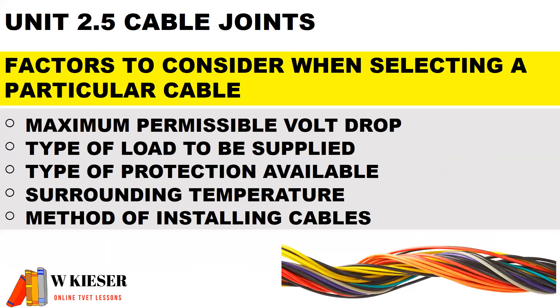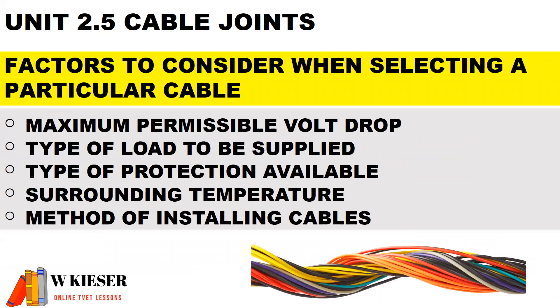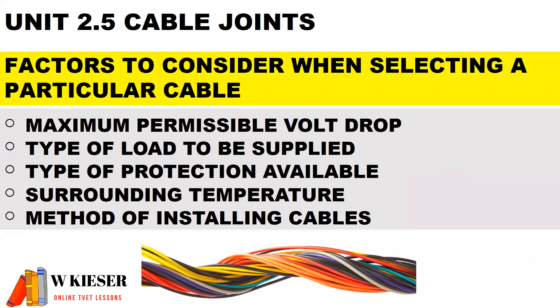Some factors to consider when selecting a cable for a particular application: what is the maximum permissible volt drop? The type of load to be supplied. The type of protection available. The surrounding temperature. And the methods of installing the cables.